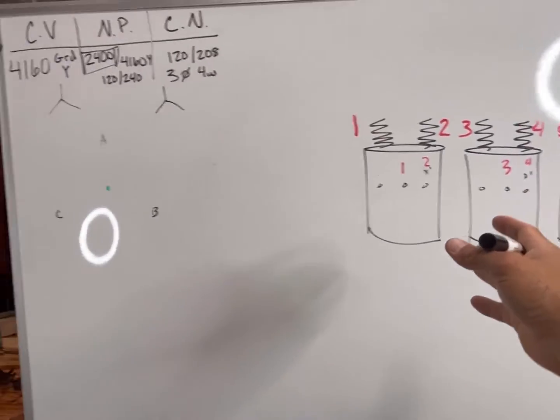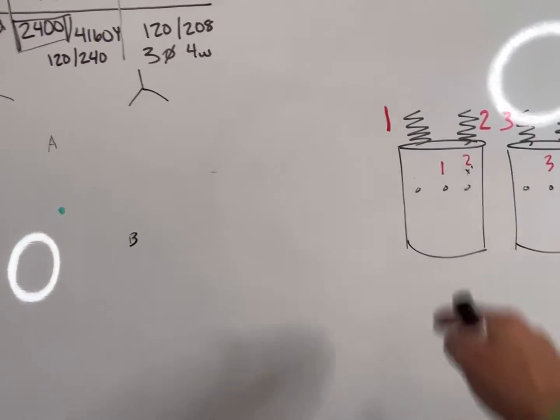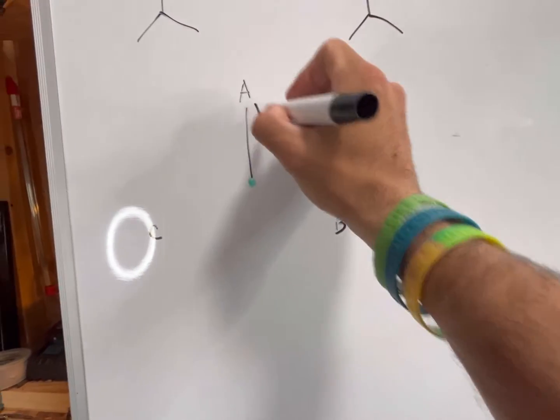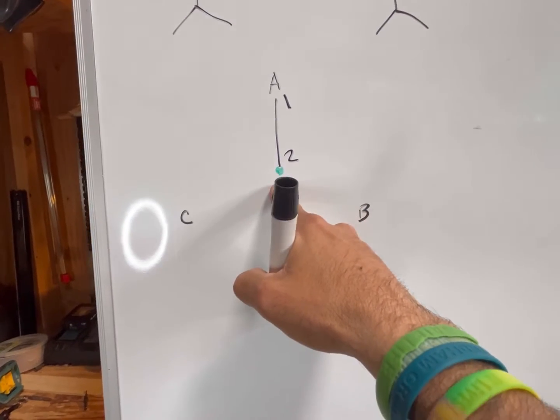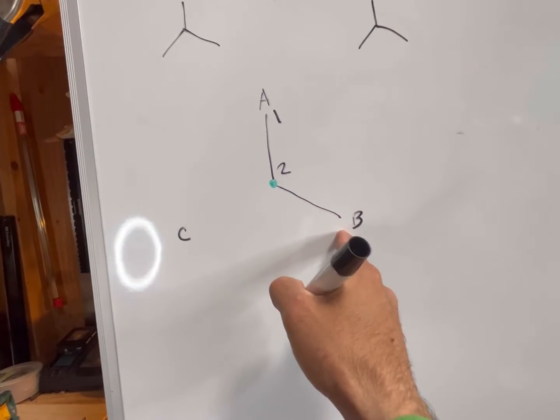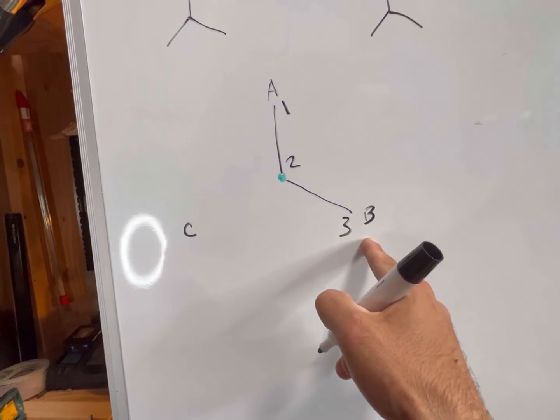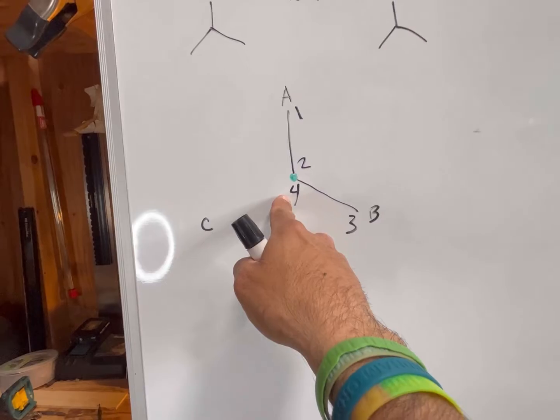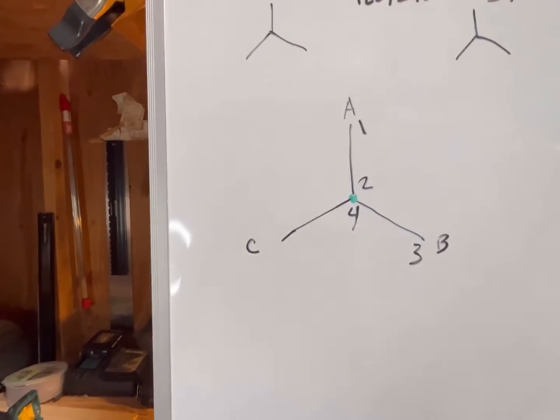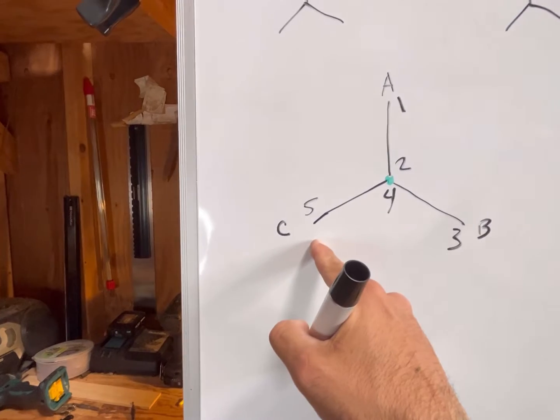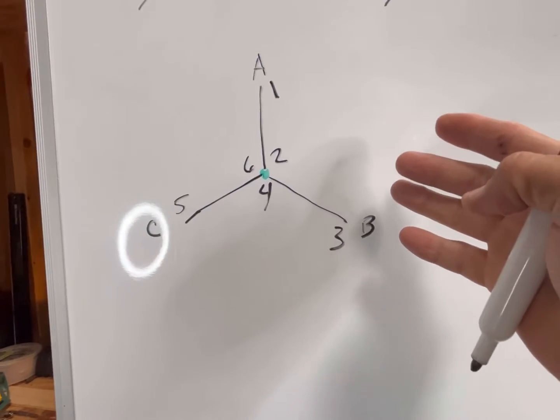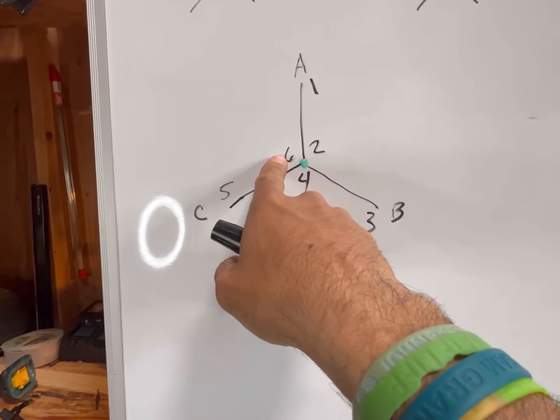Now that the bank is numbered, I can start vectoring. I take my 1-2 coil and throw it between A phase and neutral, with 1 going to A phase and 2 going to neutral. My 3-4 transformer gets fed by B phase — 3 goes to B, 4 goes to the grounded neutral. My 5-6 transformer gets fed by C phase — 5 goes to C phase, 6 goes to the grounded neutral.